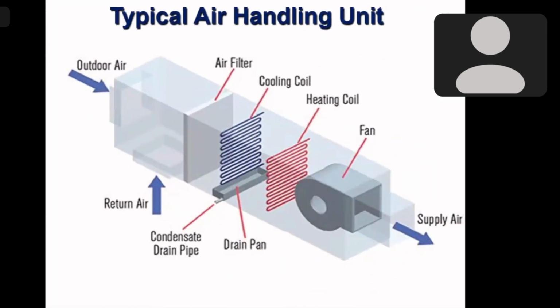Yes, this is an air handling unit. First of all, you see the most discussed component of the air handling unit, the cooling coil. The cooling coil can have cold refrigerant gas within it if it's a direct expansion system, and if it's a chilled water system, it will have chilled water in it. Then we have return air coming into the air handling unit. We mix outdoor air; you see from the left-hand side, outdoor air is entering. We mix it in this part, called the mixing box. Then we filter it because outdoor air will bring in some dust, and inside also there may be dust generation. We pass it over the cooling coil, and if you need winter heating, you also have a heating coil. Then we have a fan, and the fan supplies the air to the room through ducting. The whole thing is housed in a box, and that complete box is called an air handling unit or air handler.